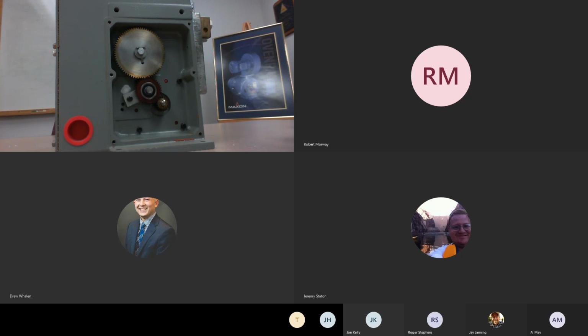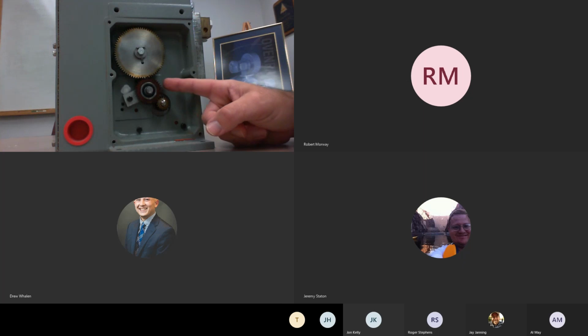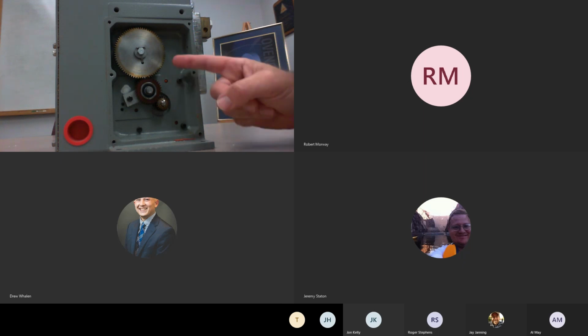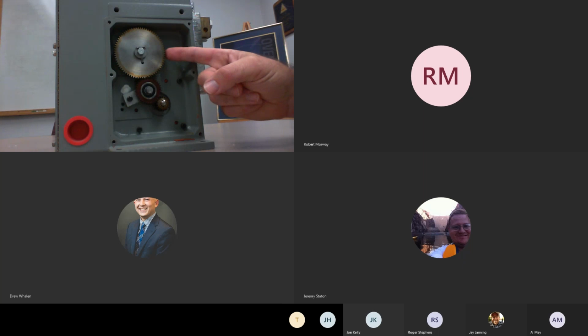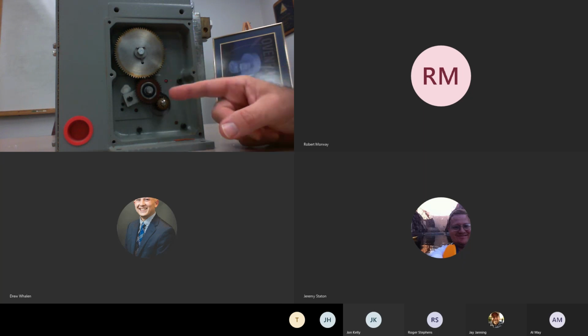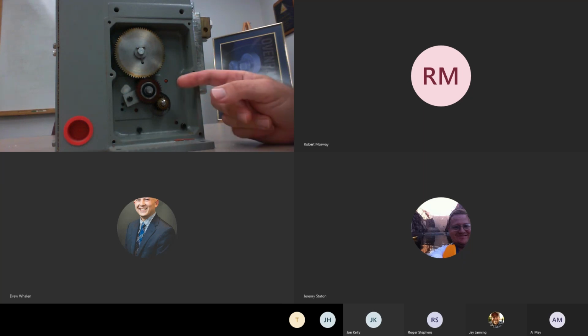Yep. So what you'll see is this front here is the 10260 actuator with the side plate removed. And inside of the side plate, you can see it's very easily accessible. It has the fiber mesh gear that is right between the output drive of the motor, the synchronous motor, and then the large metal gear that's connected to the worm gear that's inside the actuator. This fiber mesh gear here just has a C-clamp collar. So if you needed to replace that, you would remove the C-clamp collar, remove the fiber mesh gear, and then place on the new gear, and literally within minutes you can have the fiber mesh gear replaced. This would be the first place to look if the actuator was not rotating as you increase or decrease the signal.